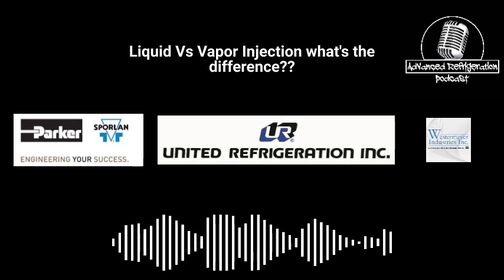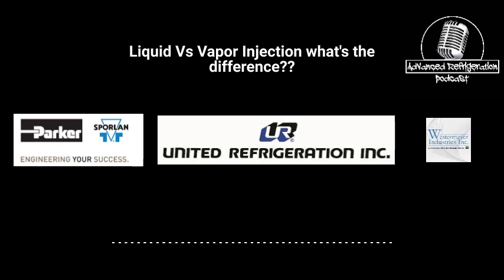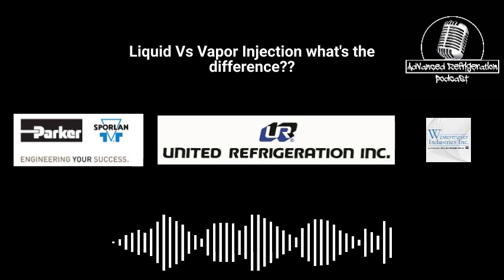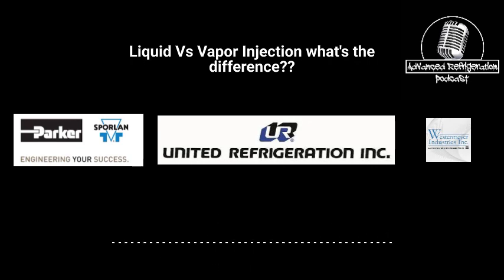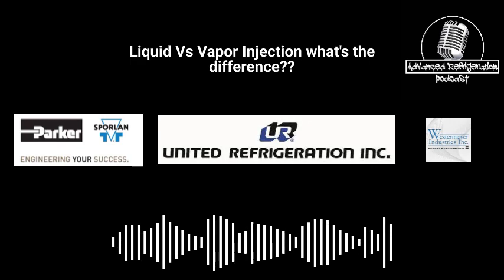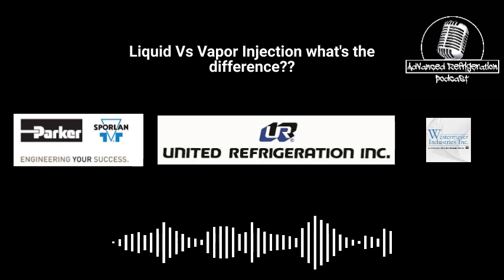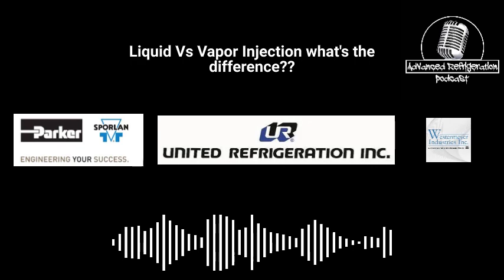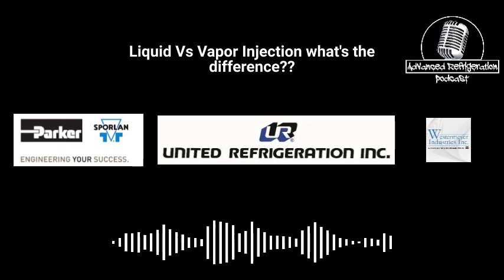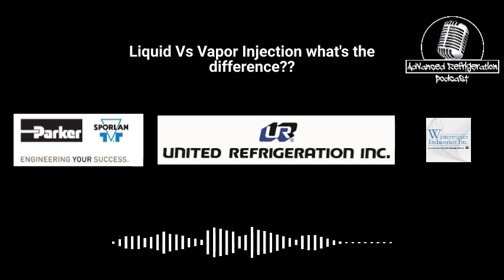If I'm running 50-degree liquid, generally I'm in the 87-pound range. I'm almost at a 50-degree evaporator. It's close to a few degree TD with the glide. Same thing with 407. It's not as efficient, but you're in the same ballpark. You've got to raise that EPR way up. You want that subcooler to run 100% and only control superheat. The EPR needs to control your actual liquid temperature going out to the cases.